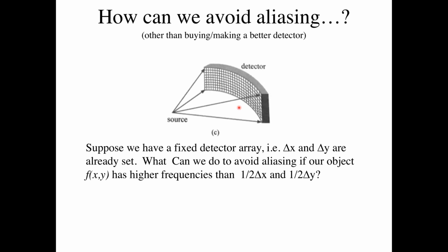Okay? And so if I have a tiny little dot, and it projects onto this screen such that that dot can be inside one detector only, and then as you move the dot around, it now gets shared between 2 detectors, and then it moves into the next detector, and so on. That will produce artifacts on a CT picture, right? Normally, you take that signal and you can do some smoothing on it to try and get rid of those artifacts.